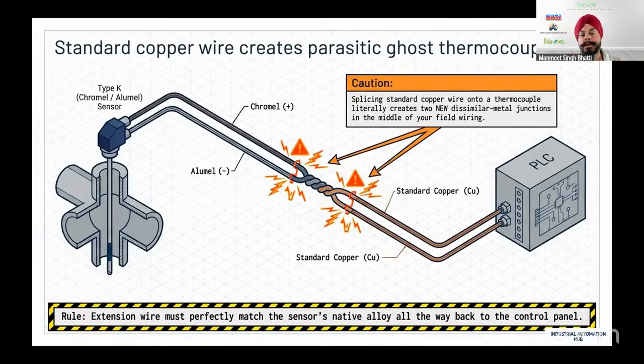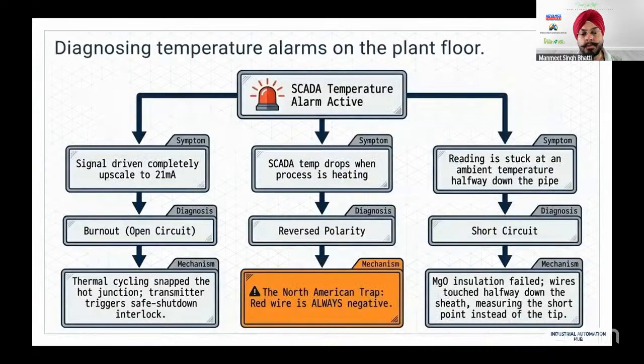So the properties of the metal that are being used for propagating that signal to the PLCs are also very, very important. So we should never use a normal copper wire to be wired to the PLC from the thermocouple. Always make sure that you have got the same set of thermocouple wire. So the same alloy or same cable metal should be used, and it should be going directly to the PLCs. That is the correct way. Otherwise, it's going to create another ghost thermocouple, and it is going to give you an output of this.